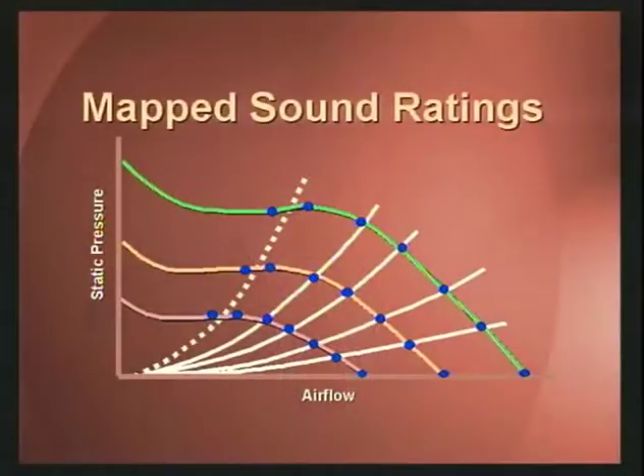I'd like to talk a little bit more about this mapped concept. If you take a look at a supply fan map, as we show in this figure, where we have the airflow on one axis and the static pressure on the other, ARI-260P requires that we test several different fan speed curves. These are constant speed curves. And along each speed curve, we take test data at equally spaced points from the stall line, which is far to the left, all the way out to wide open as defined by the manufacturer. There is a requirement on each of these test points that they cannot be any more than 5 dB apart from each other in any 1/3 octave band. This makes certain that any test data that we develop from this grid of information is very accurate.